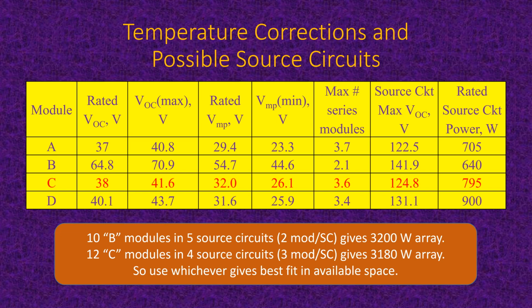And if we use module B, we would use 10 of them, and we would use 5 source circuits with 2 modules in each source circuit, and then that way we get 3,200 watts for an array. If we use module C, then we can get 4 source circuits with 3 modules in each source circuit.